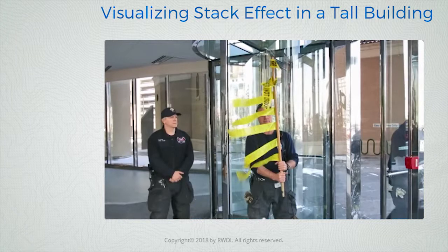So as the fire chief noted, this air movement is driven exclusively by stack effect. And one of the things I wanted to do in this screen cap that I grabbed is to just note that the kind of door that the firefighter is moving is actually what we refer to as a pressure balance door. The door is not pivoted at the edge. It is pivoted somewhere towards the center of the door, which then means that there's pressure acting on both sides of that pivot, which helps to relieve the opening force that's required to move it.